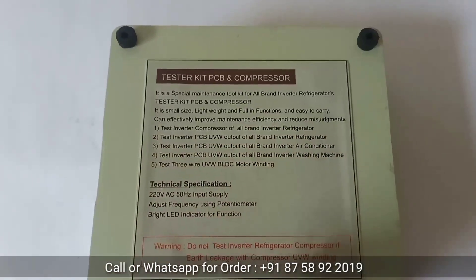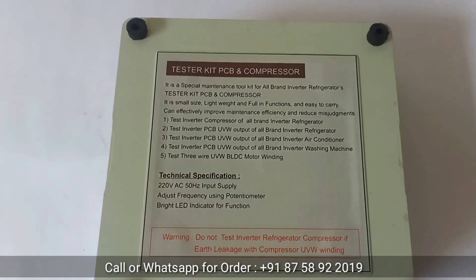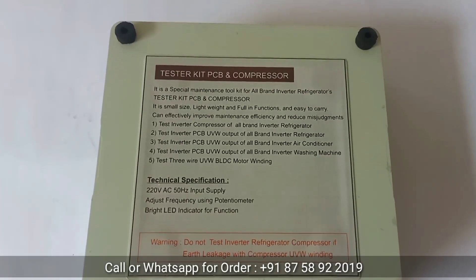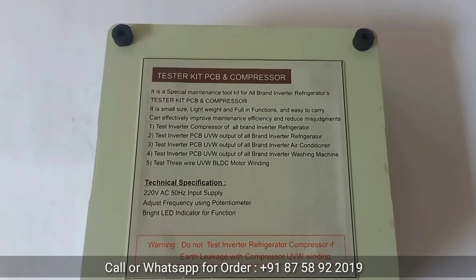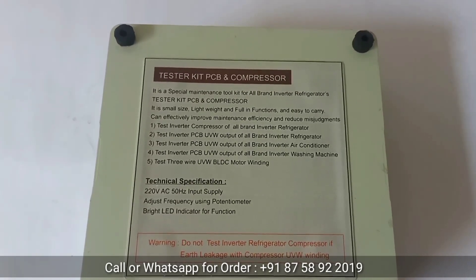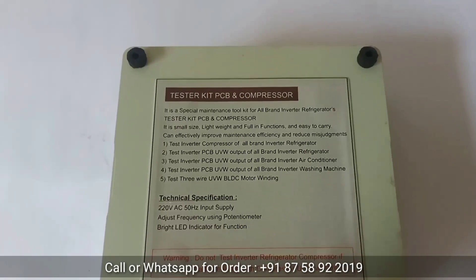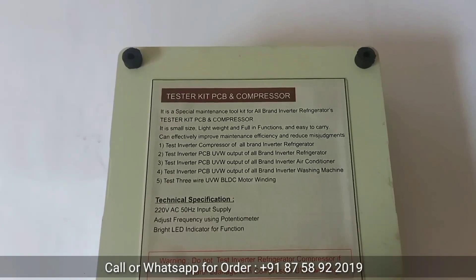Using this tester kit you can test five major functions: 1. Test inverter compressor of all-brand inverter refrigerators. 2. Test inverter PCB UVW output of all-brand inverter refrigerators. 3. Test inverter PCB UVW output of all-brand inverter air conditioners. 4. Test inverter PCB UVW output of all-brand inverter washing machines. 5. Test 3-wire UVW BLDC motor winding. All five major functions can be tested using this one tester kit.